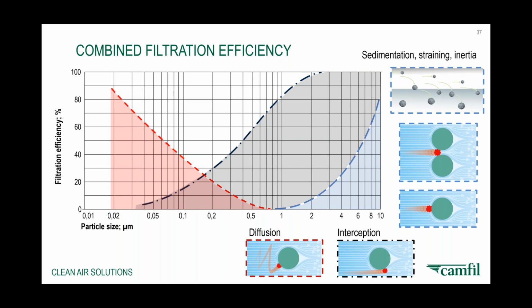That's why it's important that you look at a regular HVAC filter versus a HEPA filter, and you'll notice that there are very, very many more fibers of much smaller diameters in the makeup of a HEPA filter. And all of these various effects of the fibers, sedimentation, straining, inertia, interception, diffusion, they all work together and give it what's called a combined or total filtration efficiency. And this total filtration efficiency tends to be, as I say, all of these forces working together, but there tends to be one particle size that is the most difficult to catch.